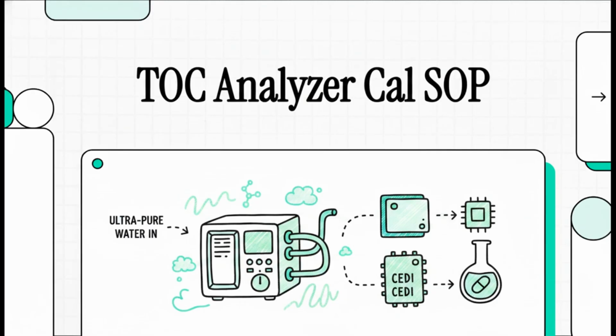Today we're diving into something that's absolutely critical out in the field, mastering the exact standard operating procedure for calibrating total organic carbon analyzers in ultra-pure water systems. You know the deal. Whether we're supplying a CDI module that needs TOC below 0.5 parts per million, or we're feeding a high-stakes semiconductor line demanding strict limits below 5 to 10 parts per billion, accurate online measurement is literally everything. So let's get right into it.